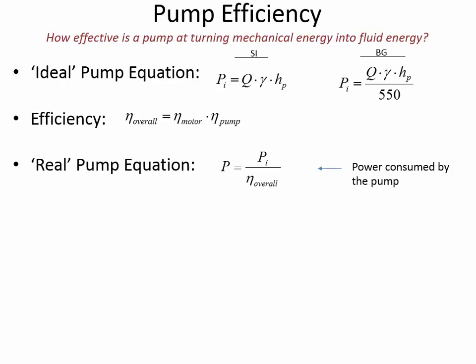Both of those are going to have some losses associated with them. In the case of the motor, when you put electricity into a motor, it's going to be heating up, and that's where the majority of the losses are. But there's also vibrations and sound, and so some of the energy is lost due to that as well. The pump also heats up. You're going to be applying energy to the shaft of the pump, and as it spins inside of the pump, there's friction, and so some energy is lost. That means your overall efficiency is just the product of the motor efficiency and the pump efficiency.